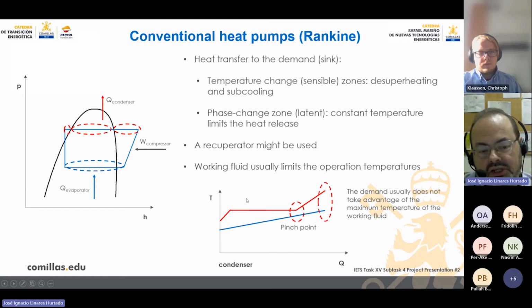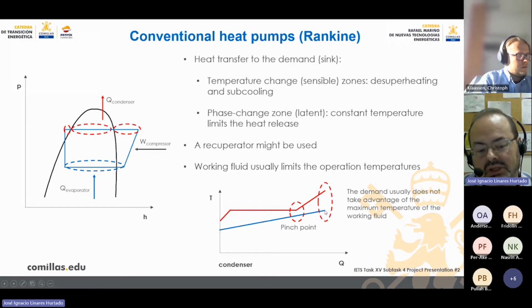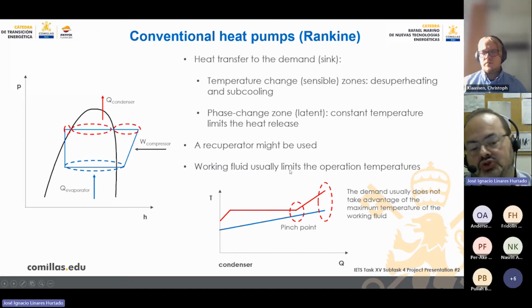This behavior can be a restriction for the heat exchanger on the demand side, as you can see here in this TQ temperature heat release profile. Here, due to the pinch point issue, the maximum temperature achievable by the heat pump is not the maximum temperature that we obtain in the fluid that we are warming up. So sometimes we have a large difference, because we can overpass this point. Sometimes even the working fluid limits the operation temperature if we want to achieve 200 degrees or more than 150 degrees. So the idea is to propose a new design to overcome all of these difficulties.